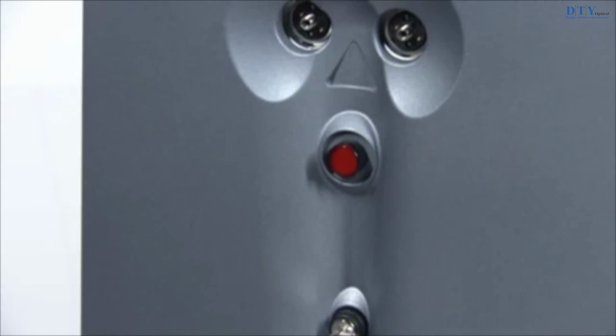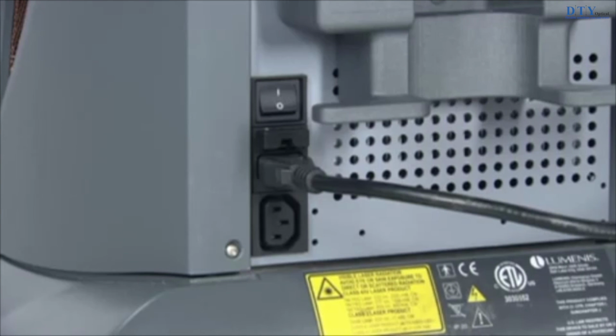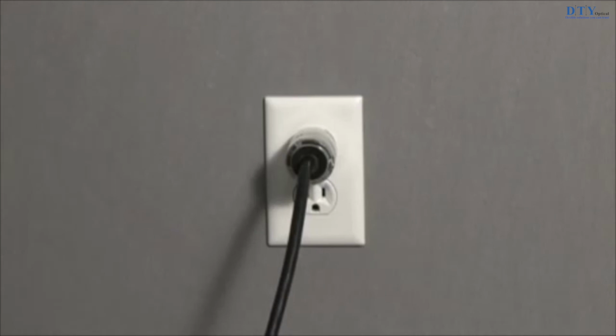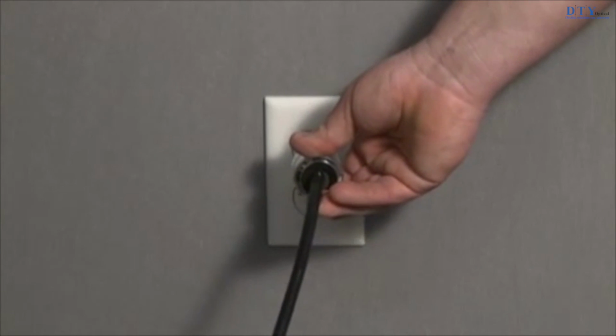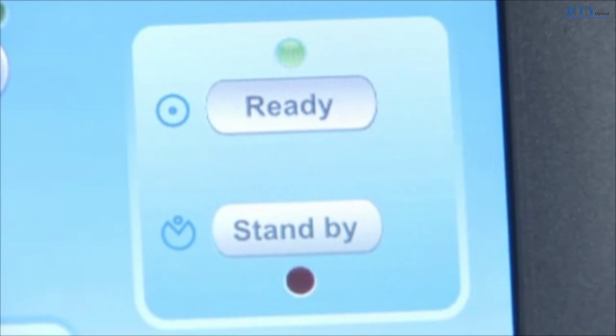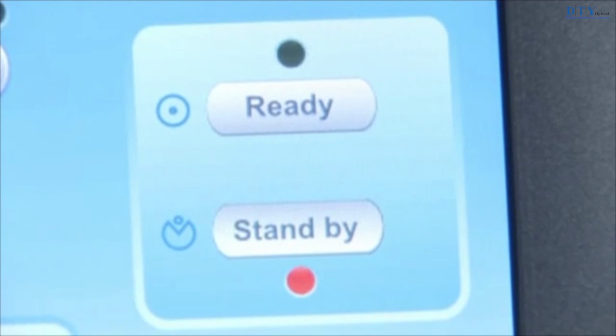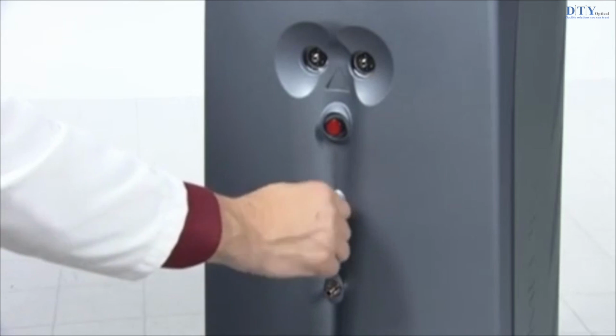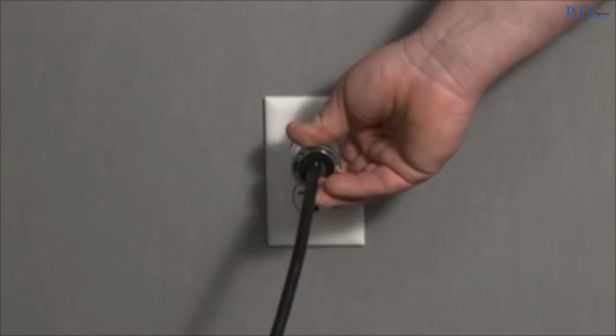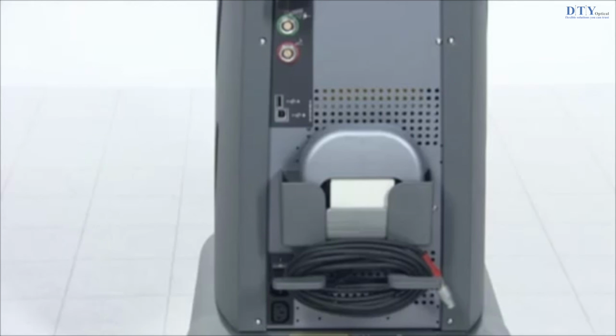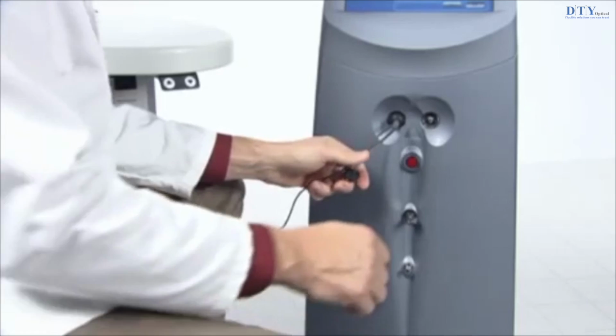In an emergency, press the emergency off button on the front of the laser console to immediately turn off the laser. When the main power cable is connected to the electrical source, some internal circuits remain energized. To de-energize all internal circuits, unplug the main power from the wall socket or turn off the main electrical service wall circuit breaker. To disconnect and store the laser components, first place the laser in standby mode. Then turn the key switch to the off position. Next, unplug the main power plug from the wall socket and wrap the power cable around the cable wrap.